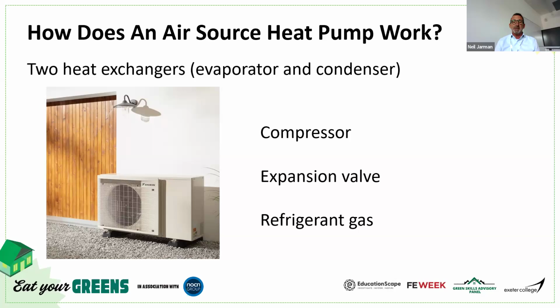and obviously a refrigerant gas, dependent upon the manufacturer. There are quite a number of different refrigerants out there. Our units at the moment are R32 refrigerant. With regards to Altherma, that's the Altherma 3. The Altherma 4, which we're launching right now, will have R290. But we're also looking at another product which will keep the unit smaller, another monoblock product like you see in the image, using R454C. Every one of those refrigerants has a different GWP, global warming potential. With regards to R32, it's 675, R454C is 148, and R290 is 3. So it's really, really low.